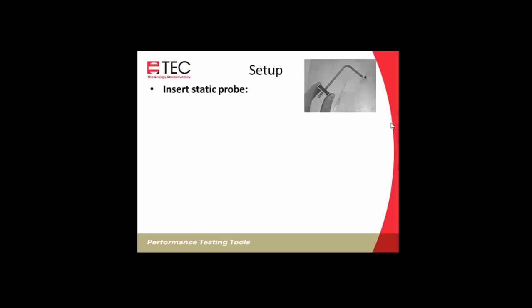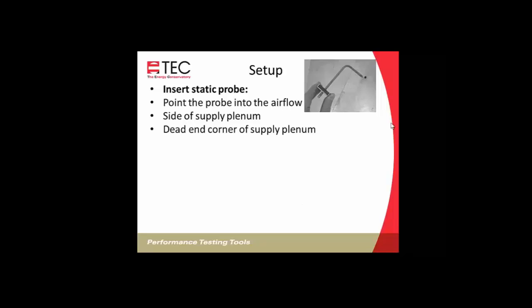Then we'll insert our static pressure probe, and we'll want that probe to be pointing into the airflow. We can install it on the side of a supply plenum, and by the side I mean if you're facing an upright air handler and there's a trunk coming towards you and a trunk going away from you, you'll want to install the static pressure probe on the side of the plenum, on either the left side or right side of the plenum, the sides that don't have the trunk lines coming off of them. You could put it in the dead end corner of a supply plenum. That's going to be a location also that's going to have a pretty stable static.